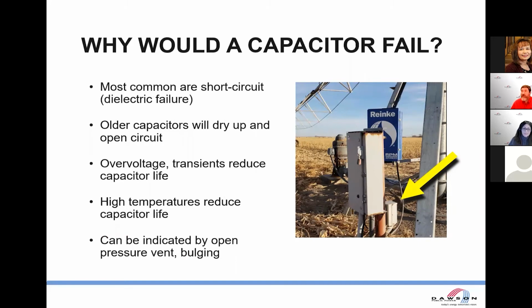High temperature can reduce capacitor life. So obviously, welcome to Nebraska. It gets a little warm in the summer, so those capacitors probably are experiencing some high temperatures, which would reduce their life. If you go to your capacitor and you open the little container that it comes in, you'll see, in the picture here, the yellow arrow points at the box which holds the capacitor on this particular service. And you see that the capacitor is bulging or it has an open pressure vent. That's a good indicator that that capacitor has failed and it's no longer doing its job.